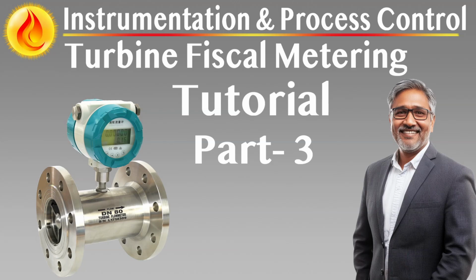Turbine meters: precision flow sensing with calibrated performance and diagnostic integrity. Performance requirements and calibration precision. Turbine meters must be selected to deliver high linearity and repeatability across a wide operating range, with performance characterized by traceable calibration. Each meter must achieve a linearity better than plus or minus 0.25% over a 10-to-1 flow range at the specified operating viscosity. Initial calibration should be performed using a liquid matching the process viscosity. However, if unavailable, water may be used with manufacturer-provided viscosity correction data.